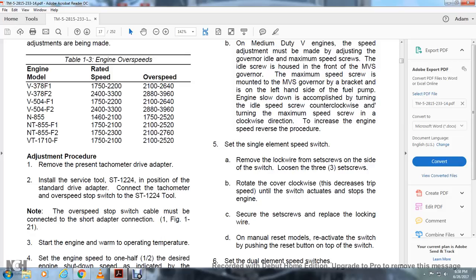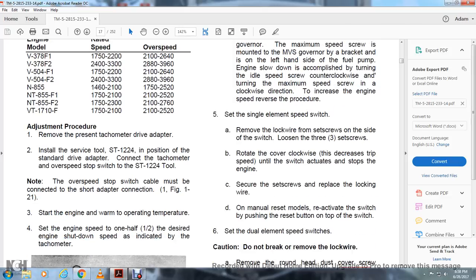Set the single element speed switch. Remove the lock wire and the set screw on the side of the switch. Loosen the 3 set screws and rotate the cover clockwise to decrease the trip speed until the switch actuates the stop of the engine. Secure the set screws and replace the locking wire. On manual reset models, reactivate the switch by pushing the reset button on the top of the switch.